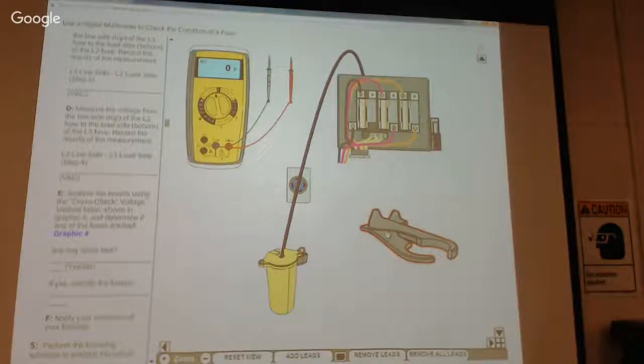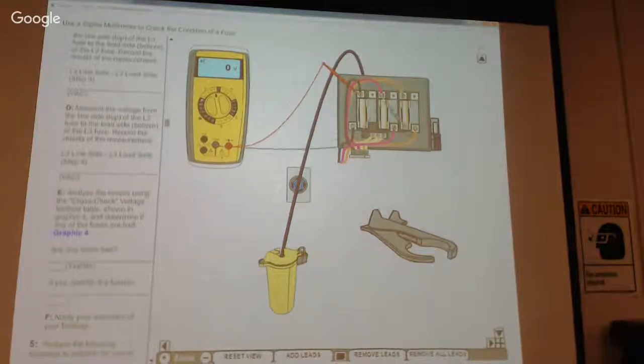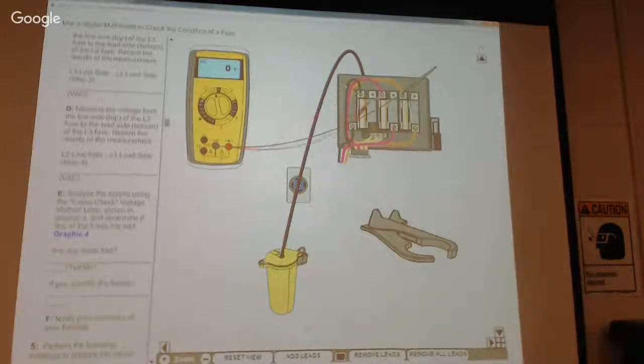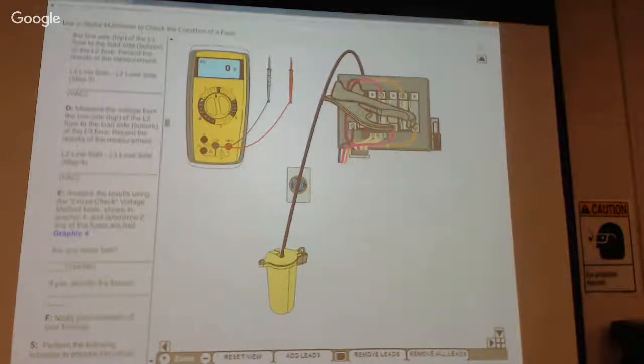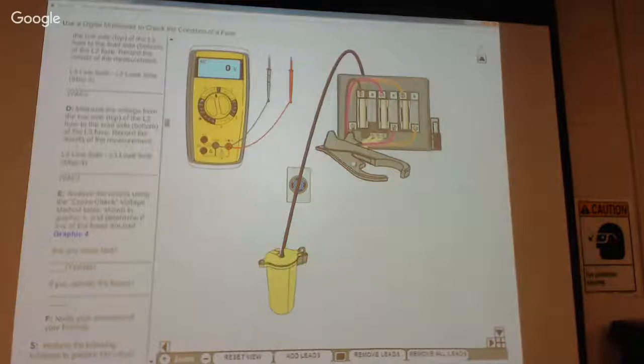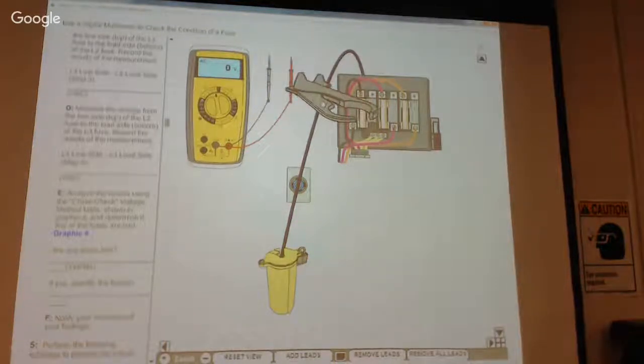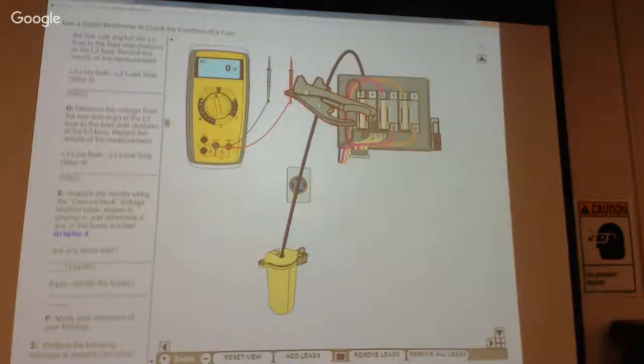The important part before we do anything else right now is to come over here and make sure that it really is off. Because this is where you can get shocked pretty bad. These are line side. This is high amperage. It's probably got 100 amp service. So it is off, so it's safe to grab. We're going to come over here and close the door. We're trying to grab a fuse, and if you do it just right, you're supposed to be able to grab a fuse out of here.